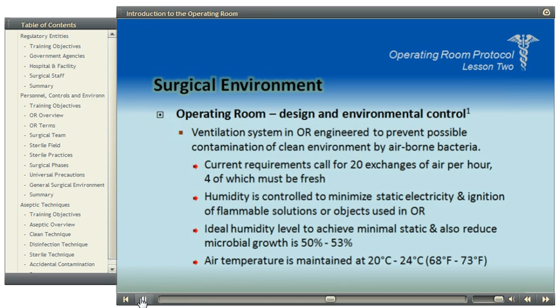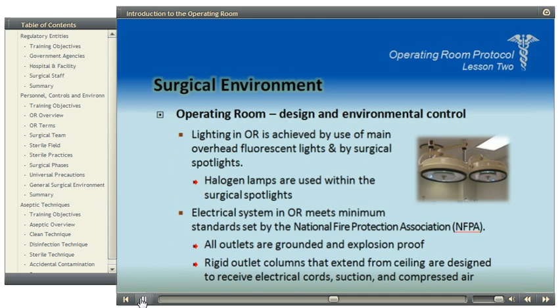Operating room, design and environmental control. Lighting in OR is achieved by use of main overhead fluorescent lights and by surgical spotlights. Halogen lamps are used within the surgical spotlights. Electrical system in OR meets minimum standards set by the National Fire Protection Association, NFPA. All outlets are grounded and explosion-proof. Rigid outlet columns that extend from ceiling are designed to receive electrical cords, suction, and compressed air.